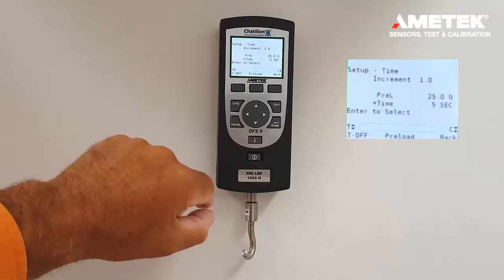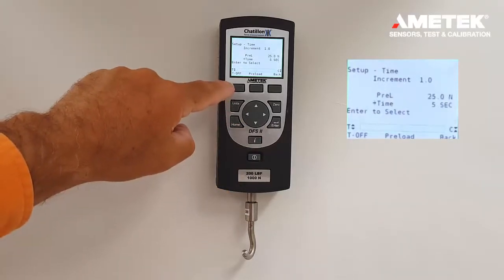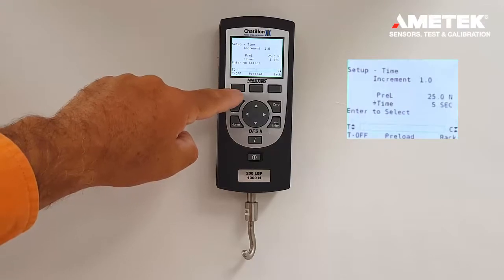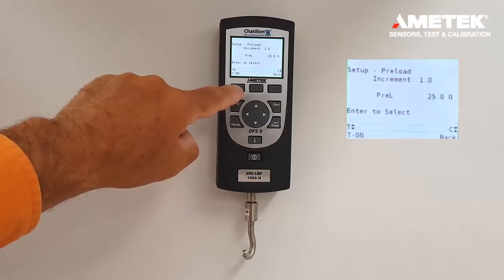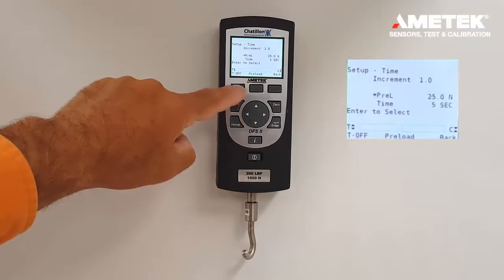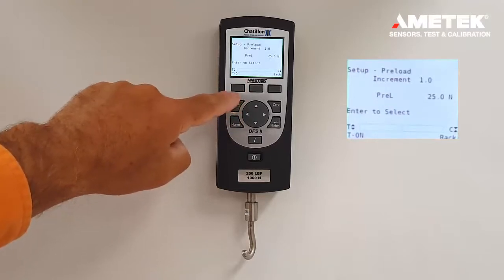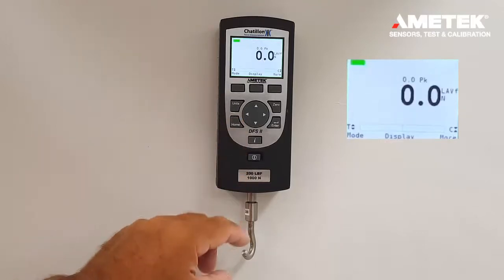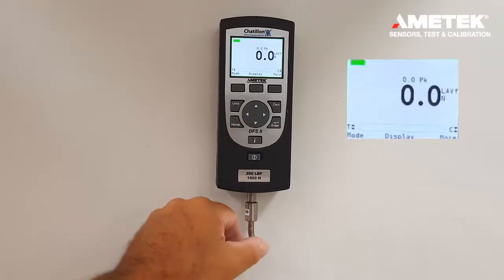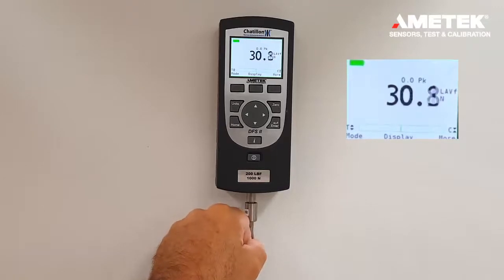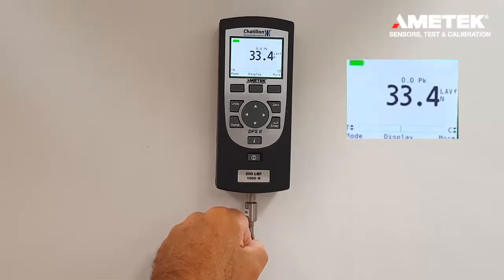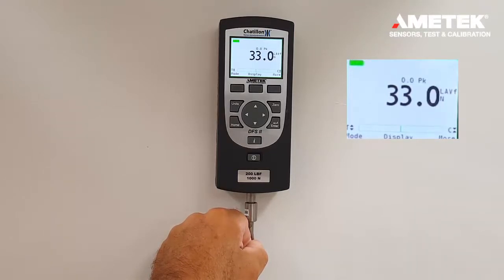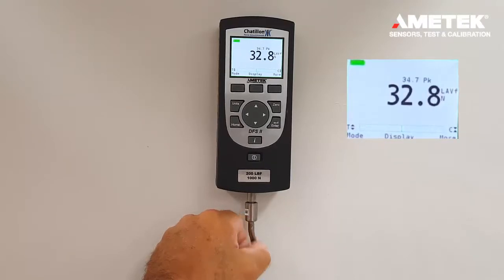Right now we are set for a preload in force and in time. Let's do the first test with the preload in force. Press the home button. We are going to go to 25 newtons and hold it, and the gauge will calculate the average above 25 newtons. As soon as the load drops below 25 newtons, it will beep twice to indicate the test has ended and capture the data.